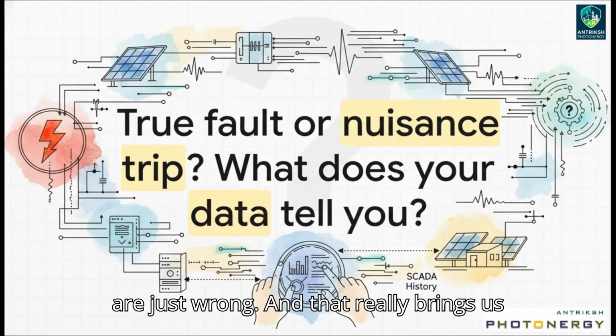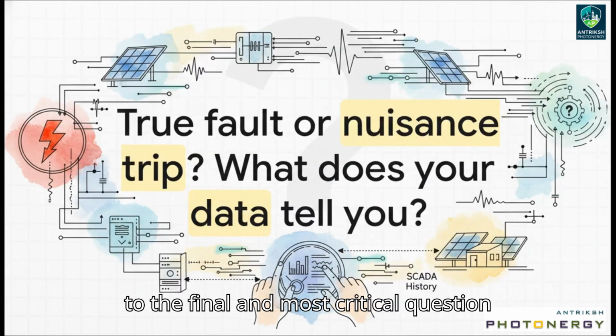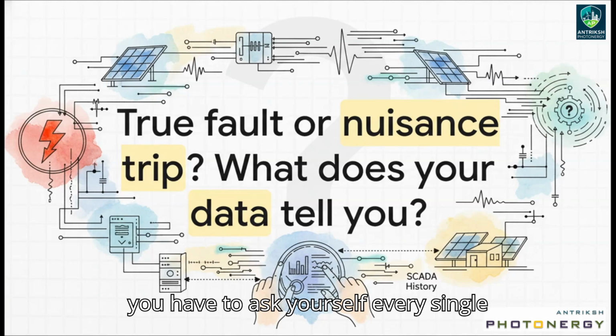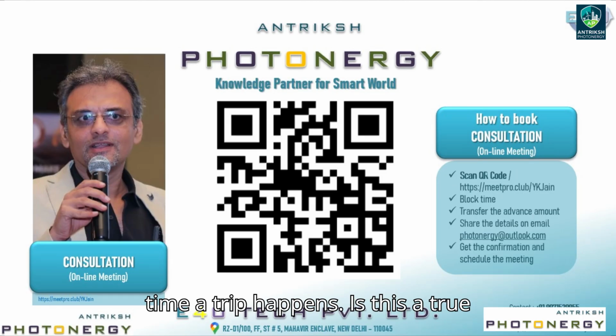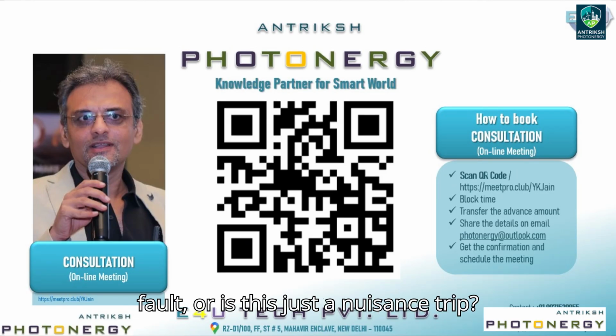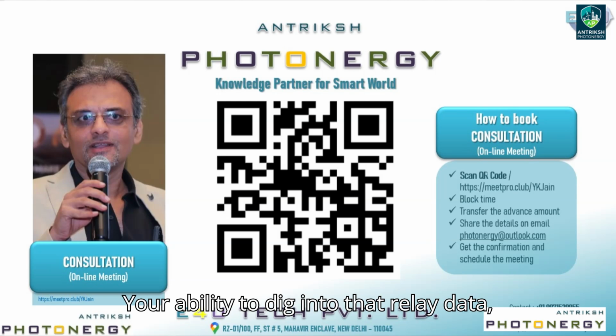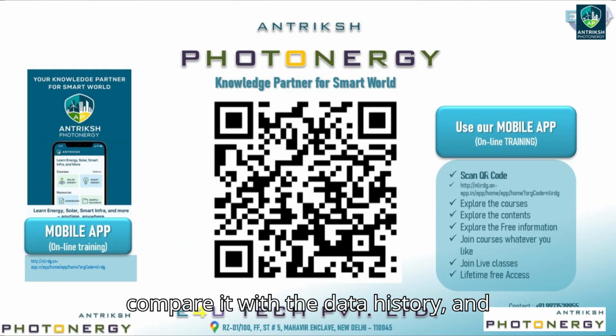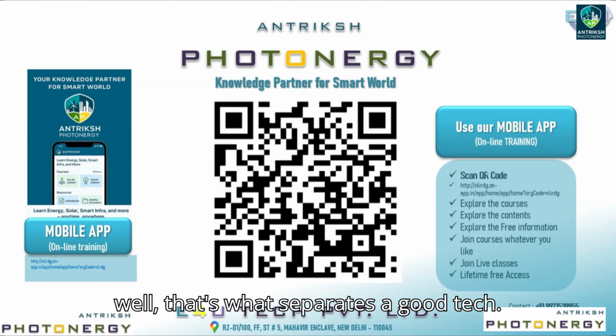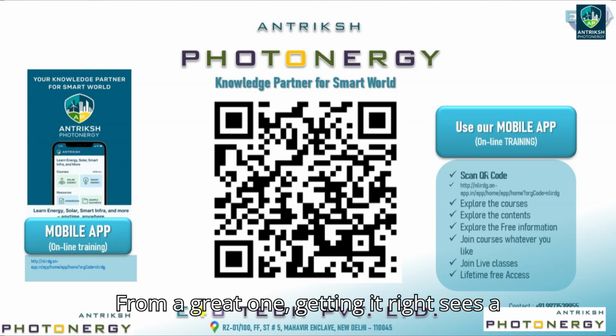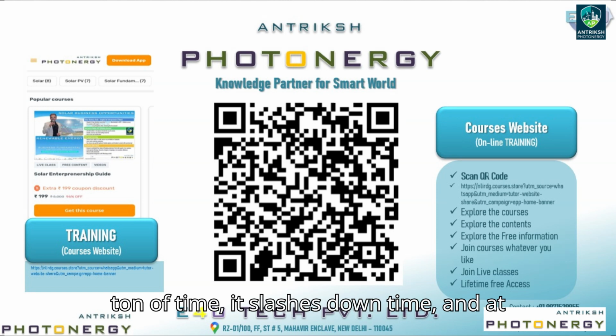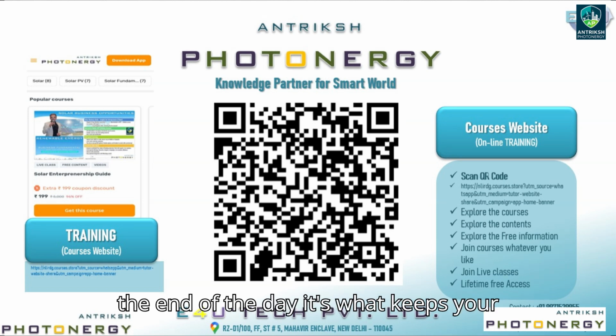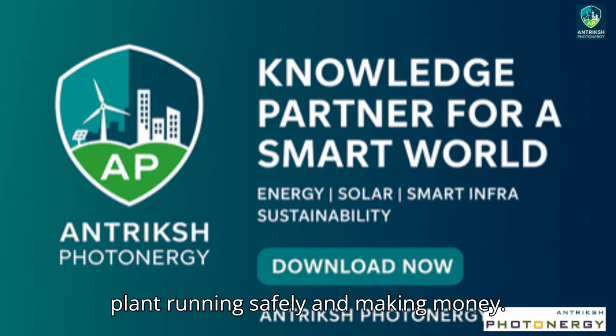And that really brings us to the final and most critical question you have to ask yourself every single time a trip happens. Is this a true fault, or is this just a nuisance trip? Your ability to dig into that relay data, compare it with the SCADA history, and make that call quickly and correctly, well, that's what separates a good tech from a great one. Getting it right saves a ton of time, it slashes downtime, and at the end of the day, it's what keeps your plant running safely and making money.